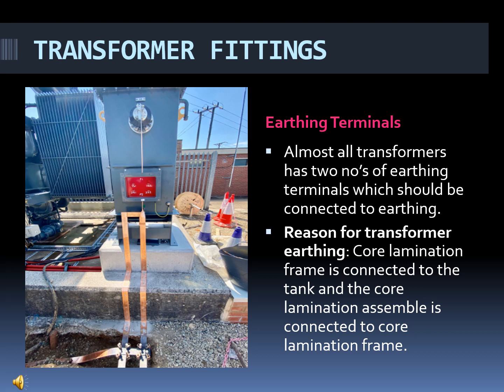There is a live supply going through the core lamination frame. At this time, there may be chances of leakage of current through the core lamination frame to the body. To protect a person from touching the tank, we must earth the transformer tank body. That is why 2 earth terminals are provided on every transformer.